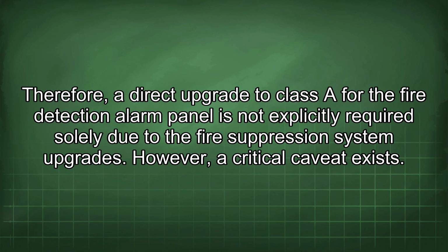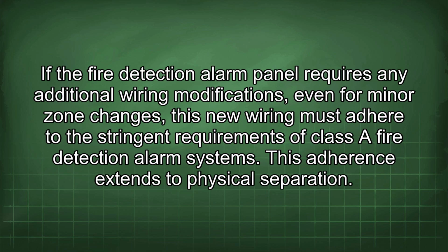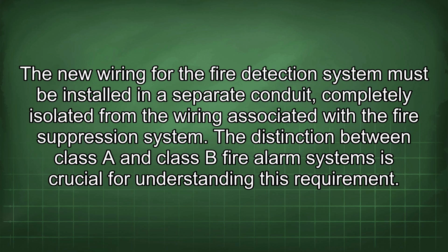However, a critical caveat exists. If the fire detection alarm panel requires any additional wiring modifications, even for minor zone changes, this new wiring must adhere to the stringent requirements of Class A fire detection alarm systems. This adherence extends to physical separation. The new wiring for the fire detection system must be installed in a separate conduit completely isolated from the wiring associated with the fire suppression system.